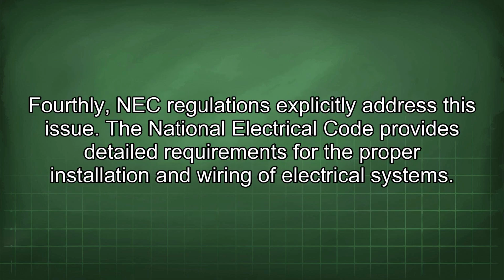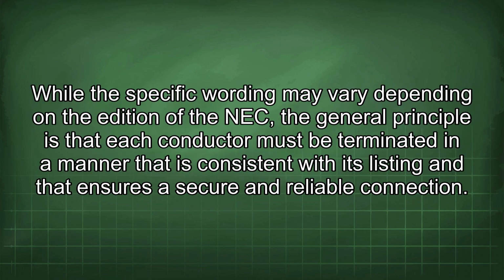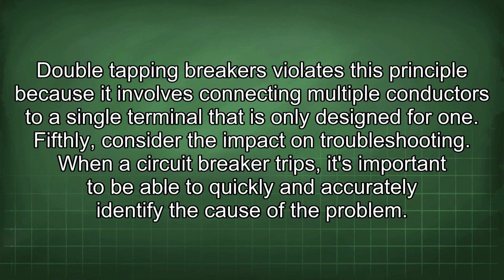Fourthly, NEC regulations explicitly address this issue. The National Electrical Code provides detailed requirements for the proper installation and wiring of electrical systems. While the specific wording may vary depending on the edition of the NEC, the general principle is that each conductor must be terminated in a manner that is consistent with its listing and that ensures a secure and reliable connection. Double tapping breakers violates this principle because it involves connecting multiple conductors to a single terminal that is only designed for one.